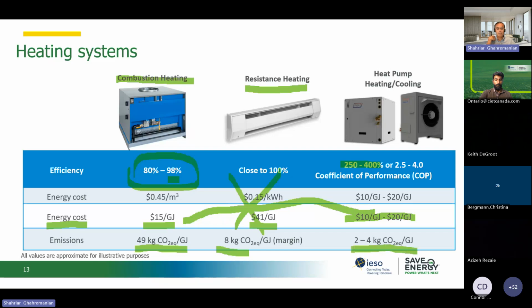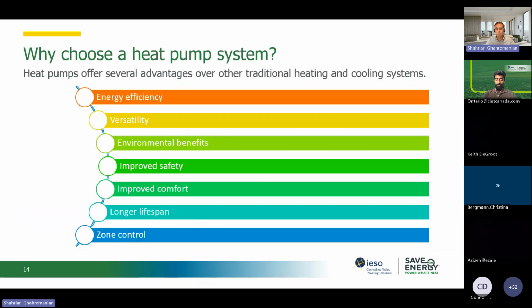But look at the heat pump. Because of the high COP, the emission from a heat pump is going to be around 2 to 4 kilograms CO2 per gigajoule. I just want to add that even for cooling, it makes it better because it's more efficient, sometimes more efficient than the existing air conditioning systems that we have. So we need to consider that. So, a large emission reduction, and the cost of utility becomes comparable. That's the message from this slide.